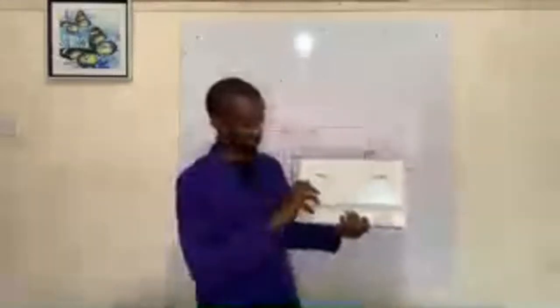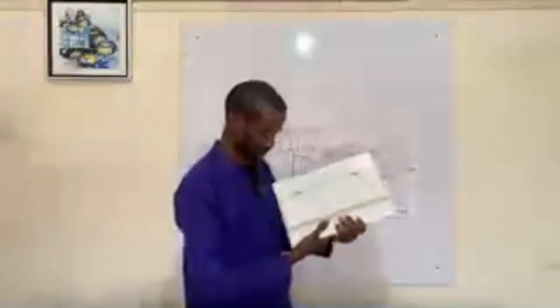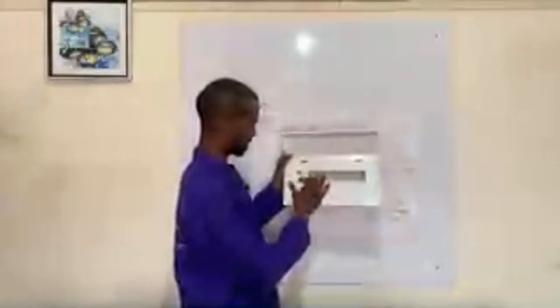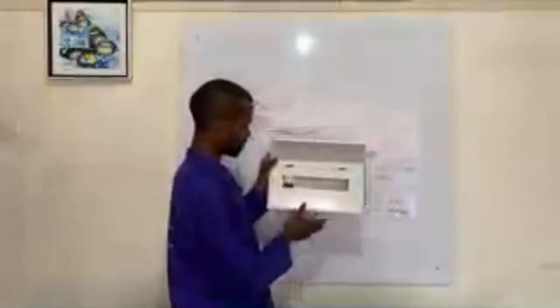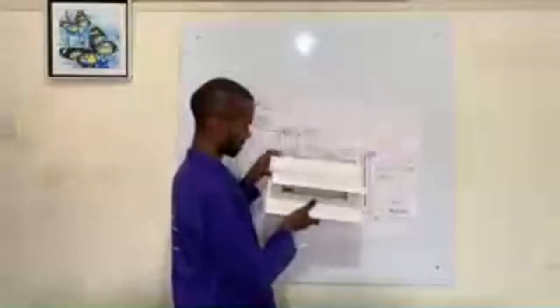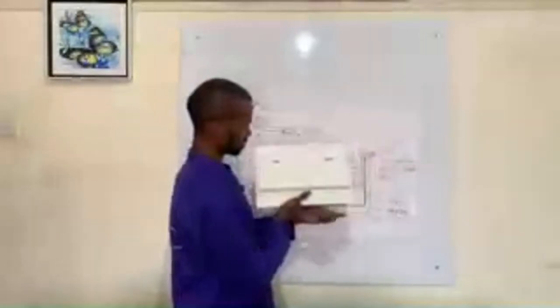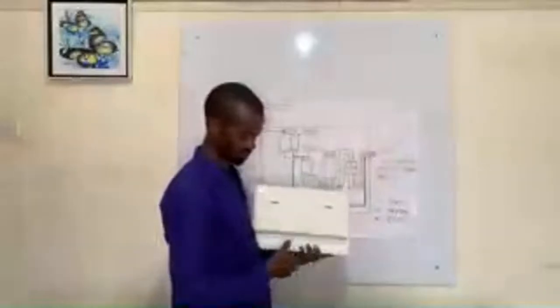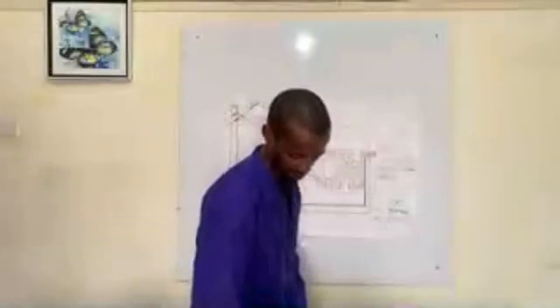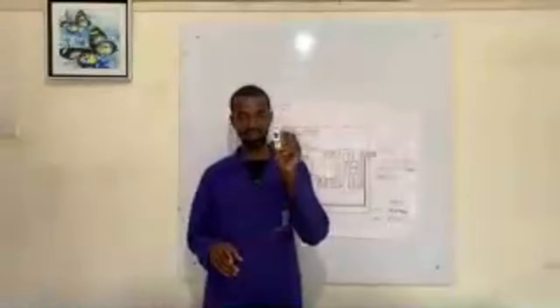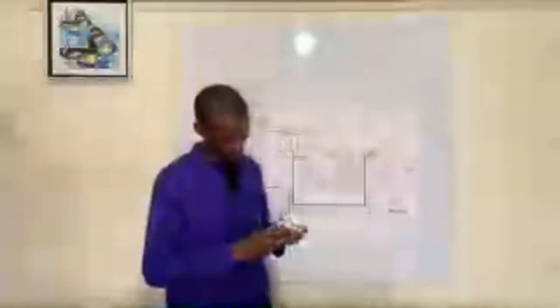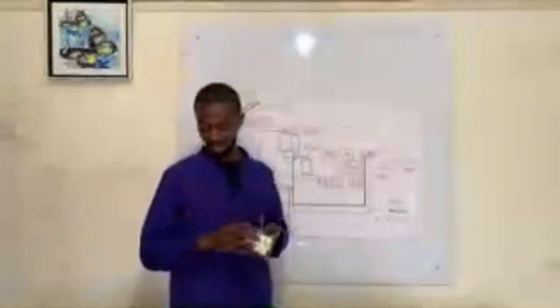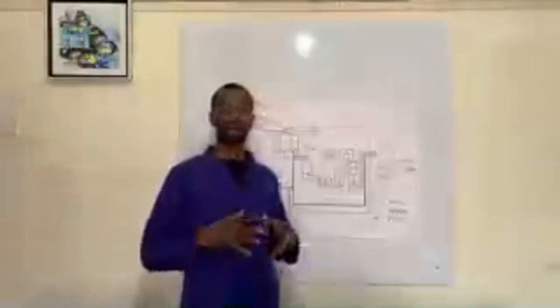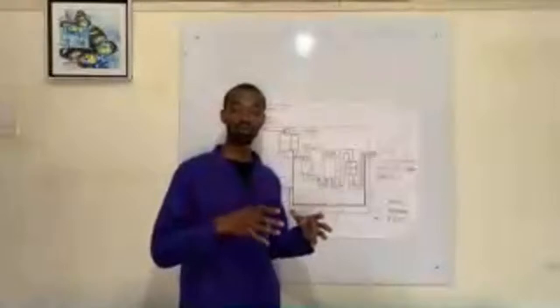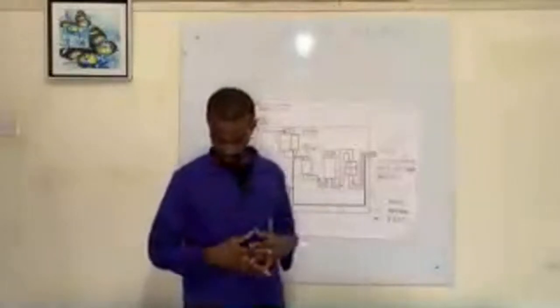I love them as large as possible. This one has got some 2 years warranty here, and it has an MCB, a DP MCB, and I can have several MCBs here. This consumer unit is a 12-way, meaning it can accommodate several MCBs or miniature circuit breakers. This is how a circuit breaker looks like. Several MCBs are usually connected depending on the circuit that they are supporting, or the circuits that have been wired in that installation - could be a house, could be an investment of any kind.